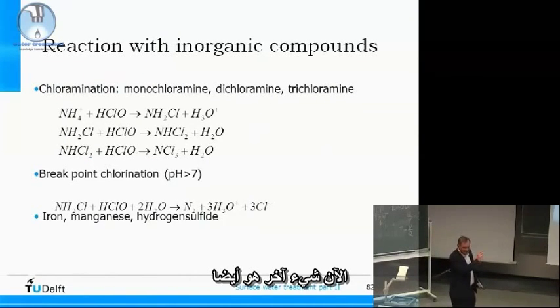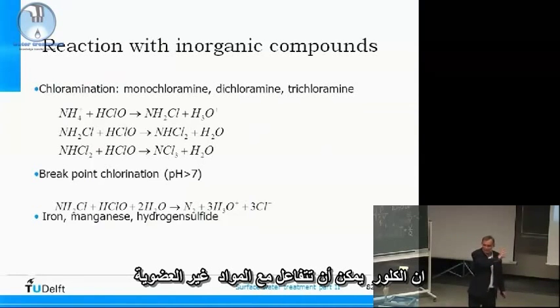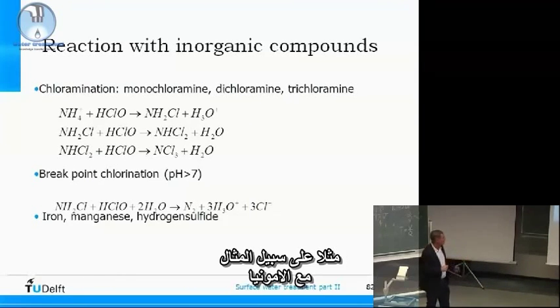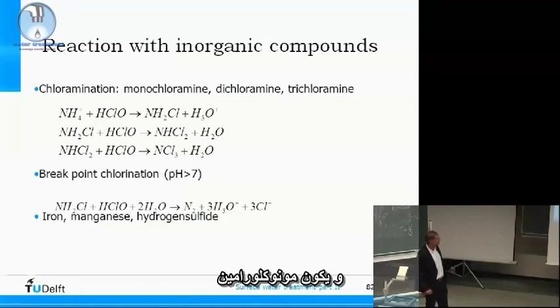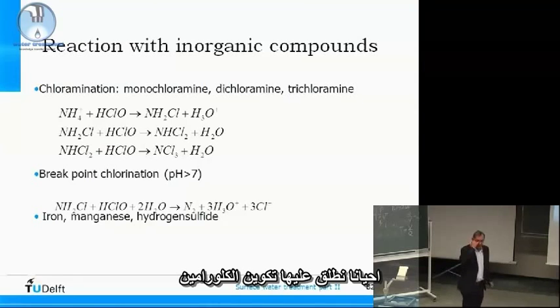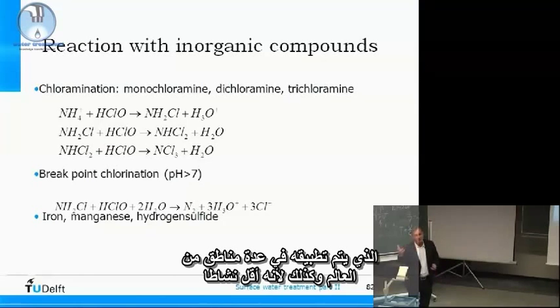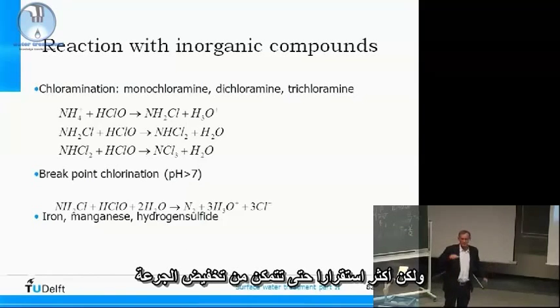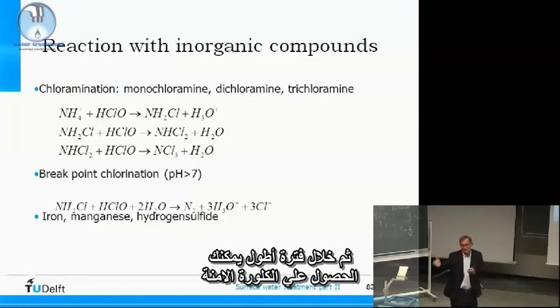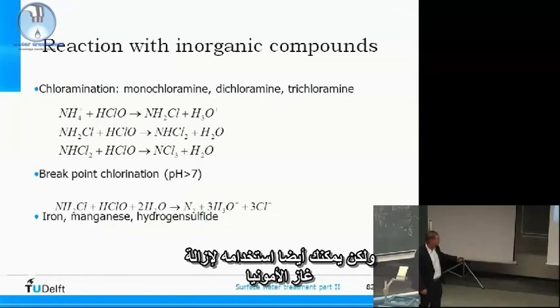Another thing is that chlorine can react with inorganic material, for example with ammonia, forming monochloramine. Sometimes we call this chloramination. It is applied in several parts of the world because it is less reactive but more stable, so you can dose less. Over a longer period, you can still maintain the safety chlorination. You can also use it to remove ammonia.